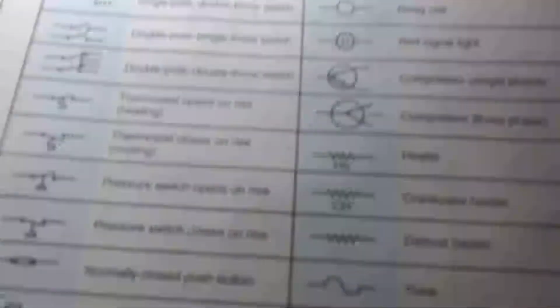Now, pressure switches. Your half circle icon stands for pressure. Okay, so just like your temperature switches, your pressure switches do the same thing. So pressure switch opens on a rise. This would be like your high pressure switches. Okay, so notice how this is when no power is applied. Your high pressure switch is open. Pressure switch closes on a rise. It's your low pressure. That means it's not going to close until we have pressure.